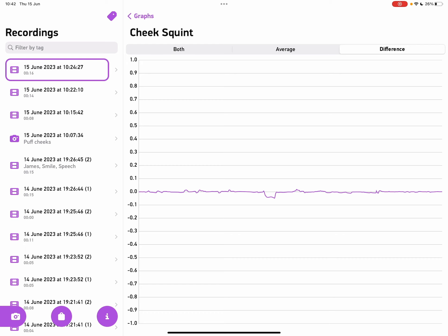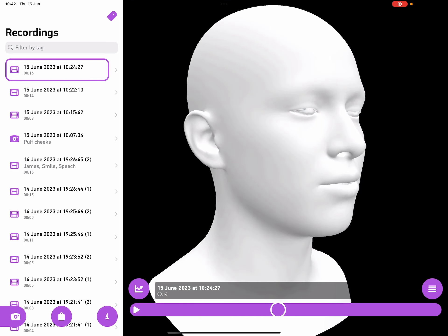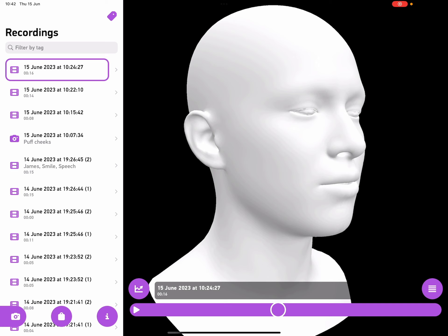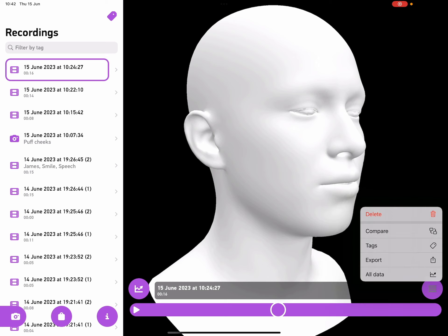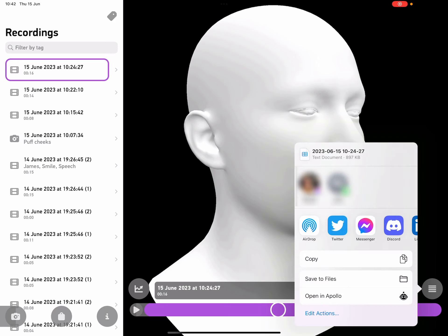I'm now going to go back to the graphs and back to the replay, tap on the menu again, and this time tap on export. This will export the data in the recording as a CSV file, which I can open in any spreadsheet I like for further analysis.